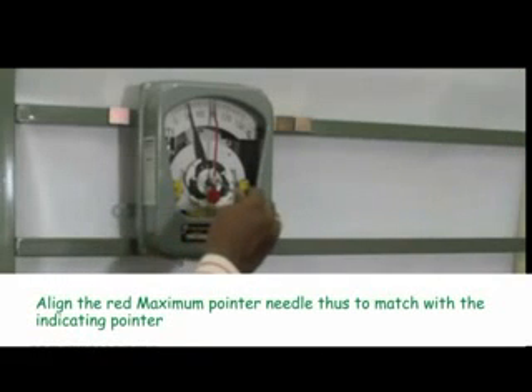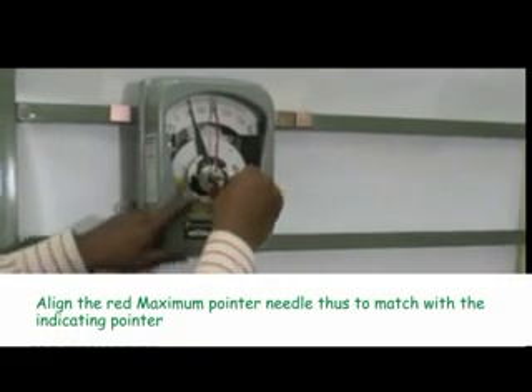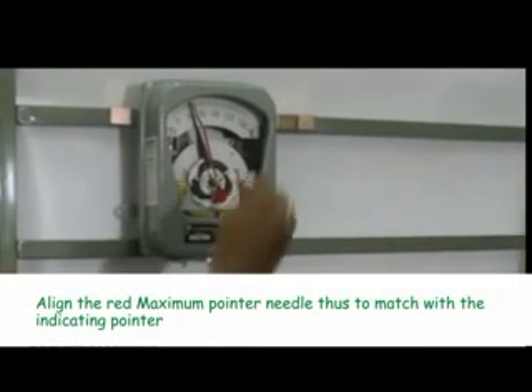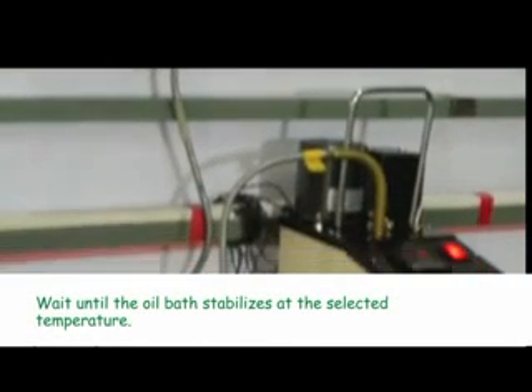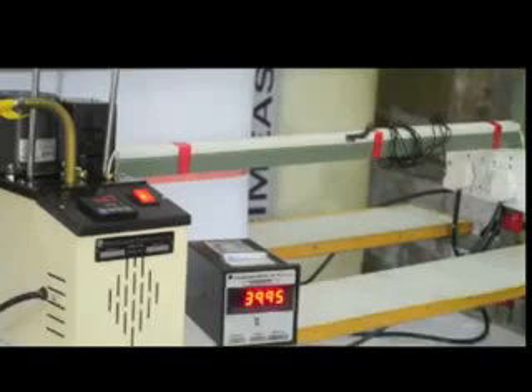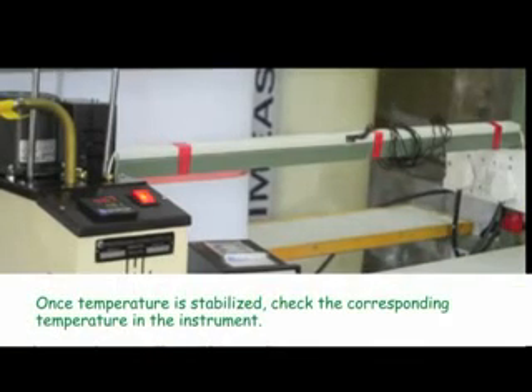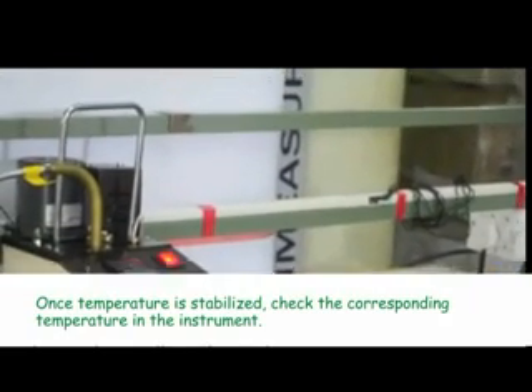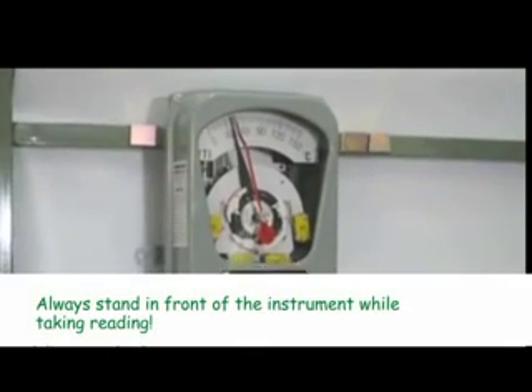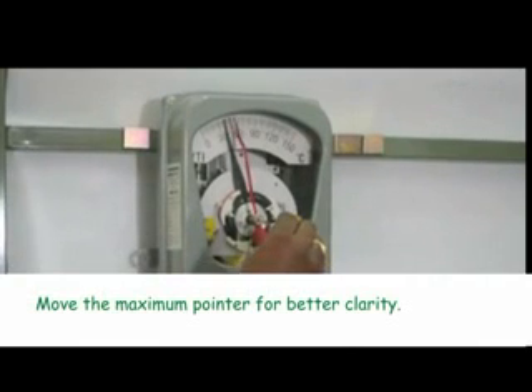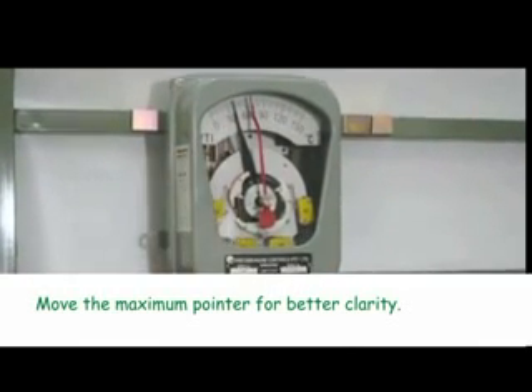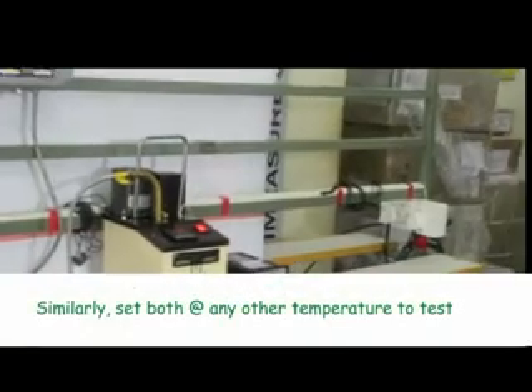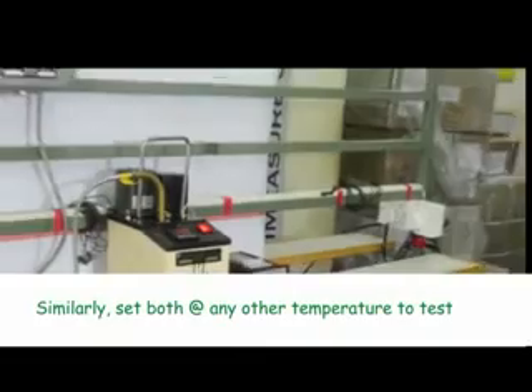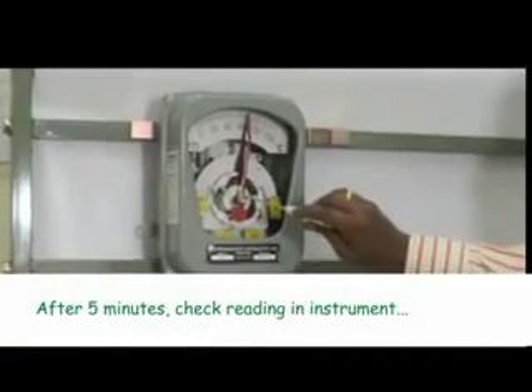Align the red maximum pointer needle to match with the indicator pointer. Wait until the oil bath stabilizes at the selected temperature. Once the temperature is stabilized, check the corresponding temperature in the instrument. Always stand in front of the instrument while taking the reading. Move the maximum pointer for better clarity. Similarly, set both at any other temperature to test. After 5 minutes, check the reading in the instrument.